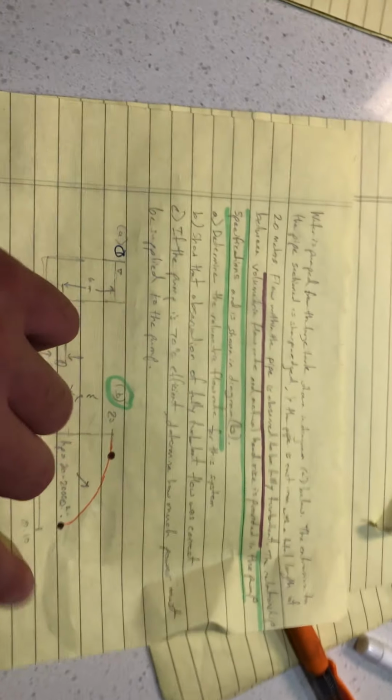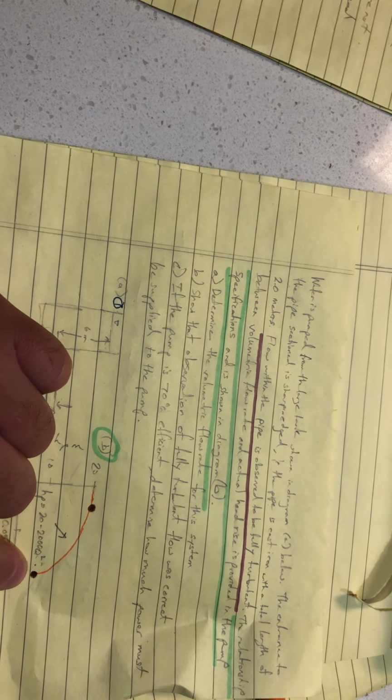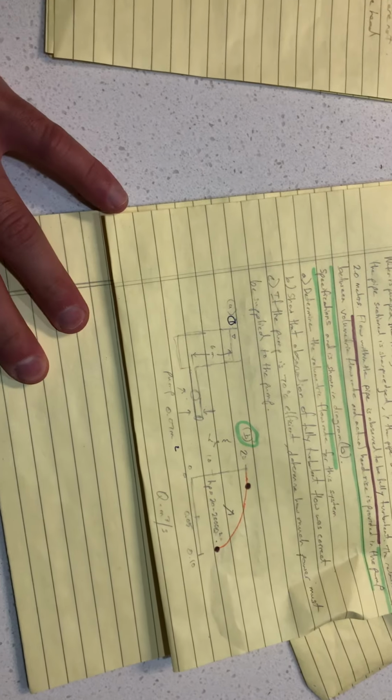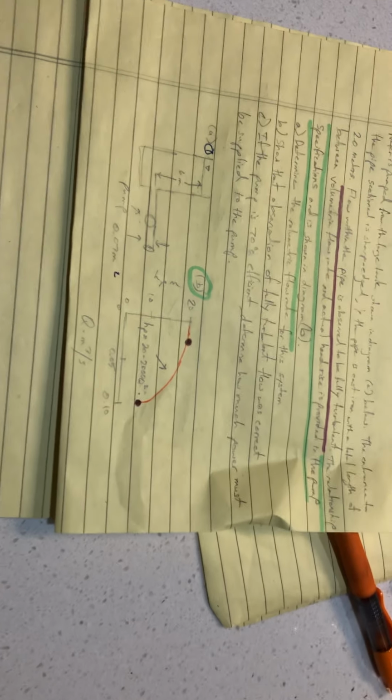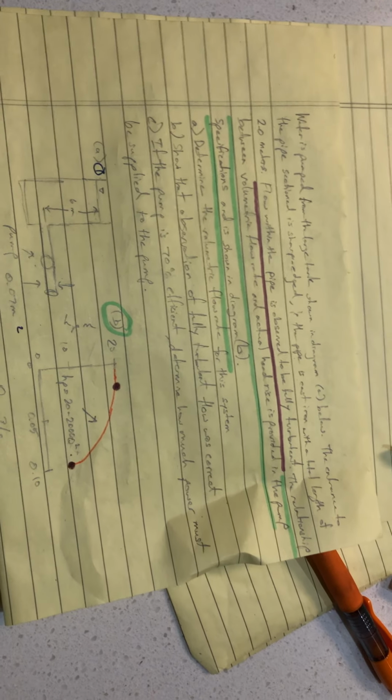Another important detail to notice is that at this dot here, we have a higher flow rate than at this dot. And when we have a higher flow rate, our water is almost moving as fast as our pump blade, so the pump doesn't really require as much work to get going. However, if you have a slow flow, the pump blades are going to be able to absorb more of that force, and so we are going to see more of a head rise when observing the slower flow rates. So I like to think of it as a car. When you're trying to get a car to accelerate, it's going to be harder when it's stationary versus when it's moving at a really high speed. So it's the same thing with these blades when the fluid comes into contact with them.